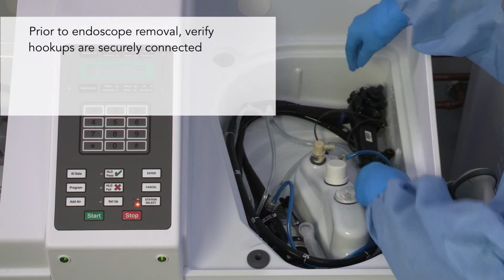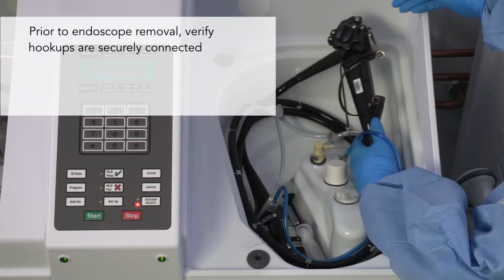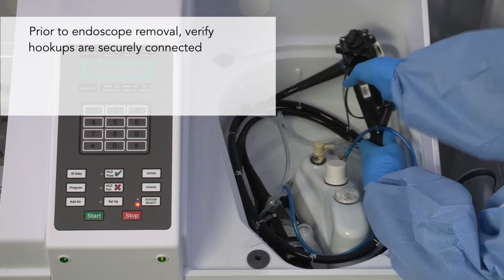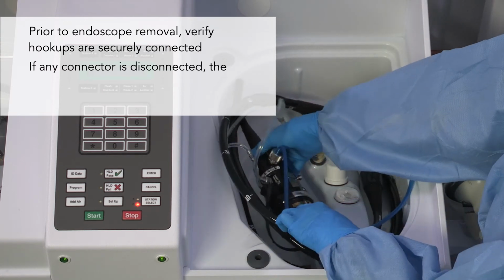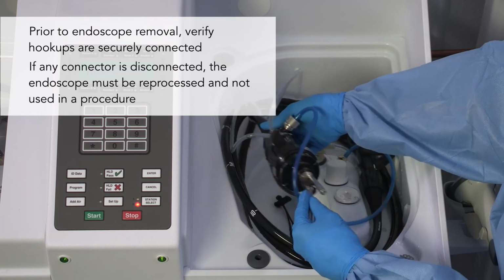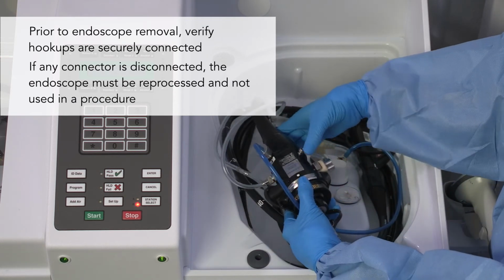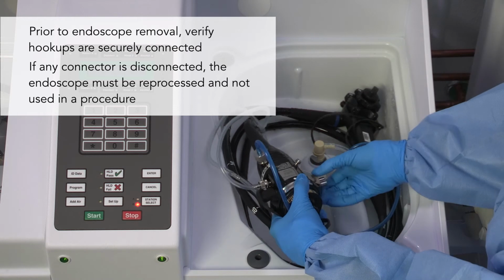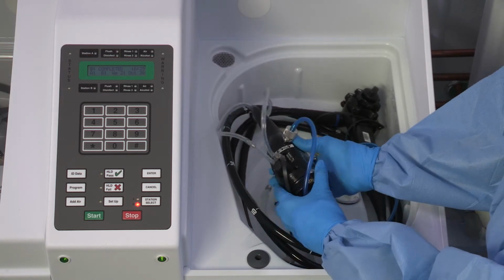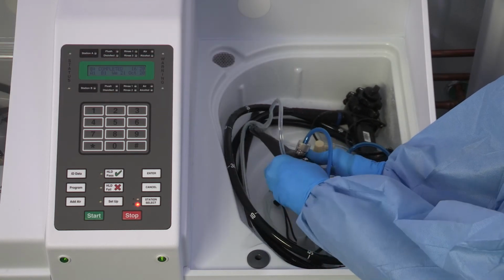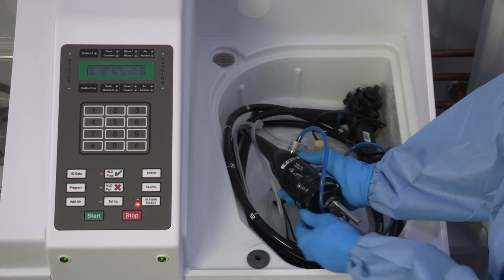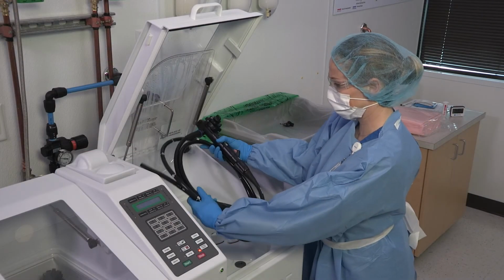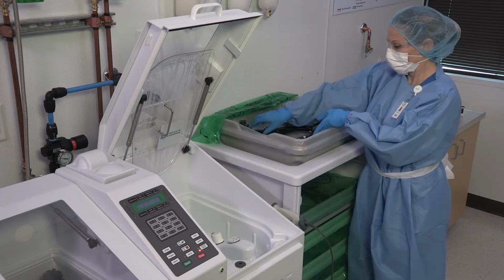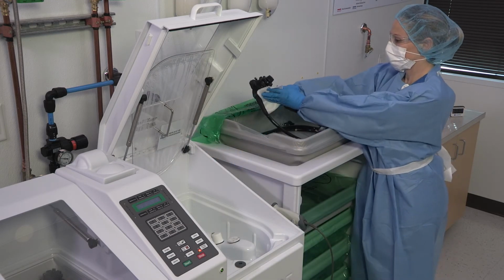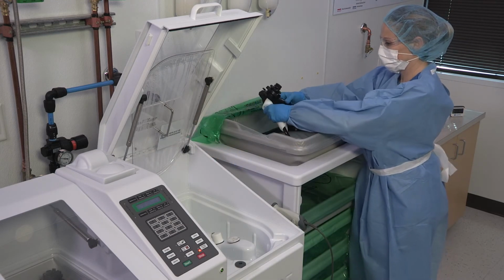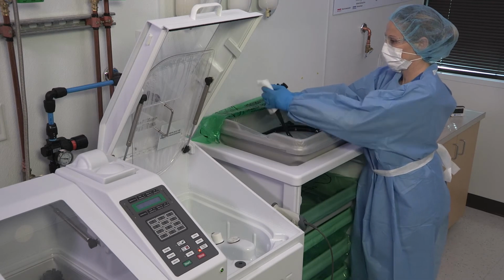Prior to removing the endoscope from the basin, it is critical to verify the hookups are securely connected to the endoscope. If any connector is disconnected, the endoscope must be reprocessed and not used in a procedure. If all hookup connectors are still securely connected, remove all connectors from the endoscope and remove the endoscope from the basin. Thoroughly dry all surfaces of the endoscope using a clean, unused, lint-free cloth.